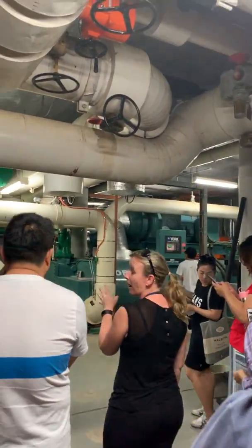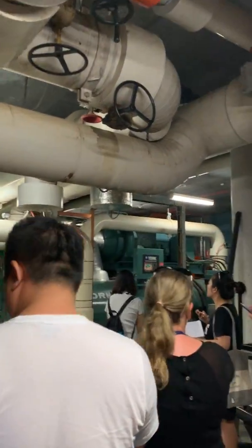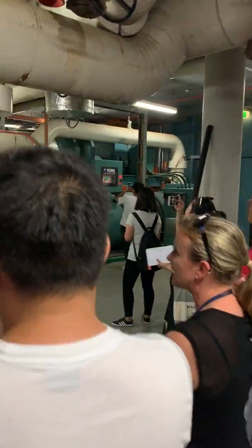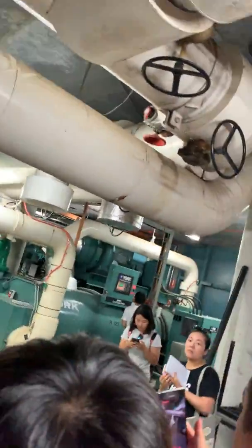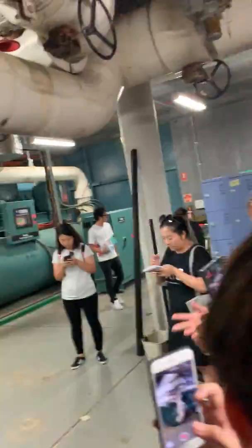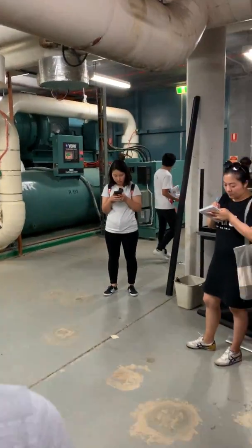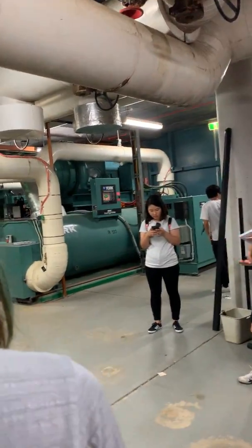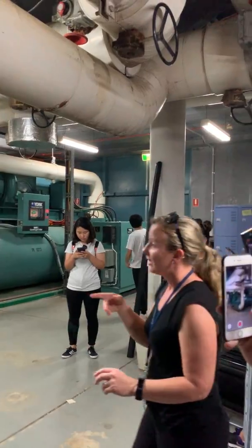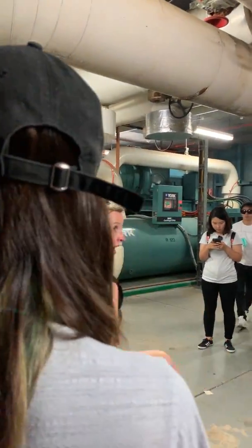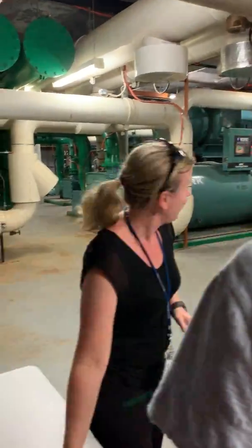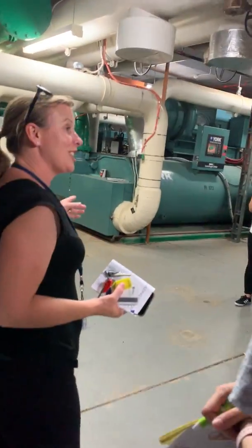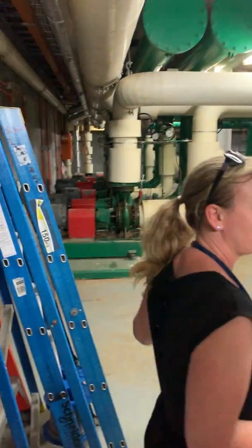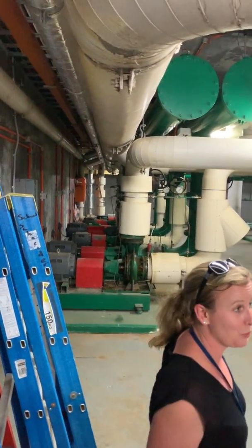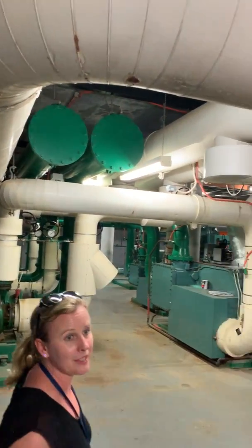We've also got green pipes in here. They're your condenser water. They're connected to the cooling towers, which are located outside. Each of the chillers has 2 green pipes connected. So water going out to the cooling tower, water coming back in. You can also see on this left-hand side, these are pumps, and each chiller has 2 pumps. One pump's for the chilled water, the other pump is for the condenser water.